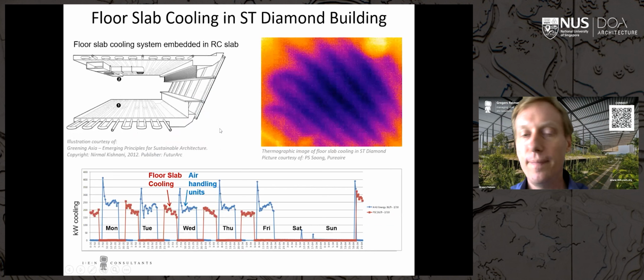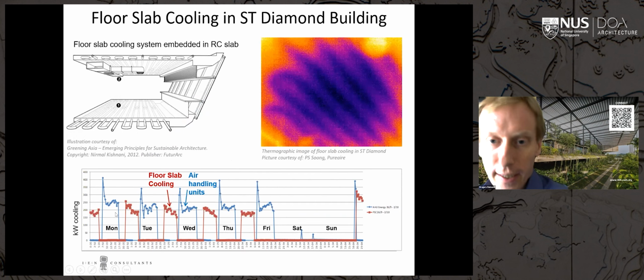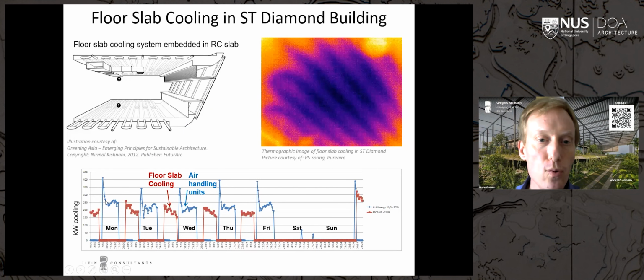For the floor slab cooling system, we did some measurements because this is quite new here in the tropics. So one measurement is shown here, which is measuring the cooling that is delivered to the building over 1 week. So the blue color graph, that is the normal air conditioning in the air handling unit and the ducts. So this is during the daytime. The red one shows the floor slab cooling. So let's say we take Wednesday. So on Wednesday, around 7 in the morning, the normal aircon starts up. But the night leading up to Wednesday, so starting around 10 p.m. at night, so that's Tuesday night, 10 p.m., we had actually already started the slab cooling system.